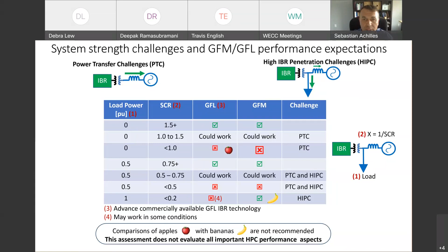So the aspects where we do expect grid forming to do differently than grid following are related to behavior to angle jumps and response to rate of change of frequency. Those 2 aspects were mentioned already. I'm going to go quickly through this. In principle, we see requirements where inverter-based resources have to tolerate an angle jump without tripping. That's something that grid following and grid forming can do. The expectation is that grid forming would help the system by opposing the angle changes. That's something where grid forming has a clear differentiation with respect to grid following. Rate of change of frequency is a similar concept and was described before.